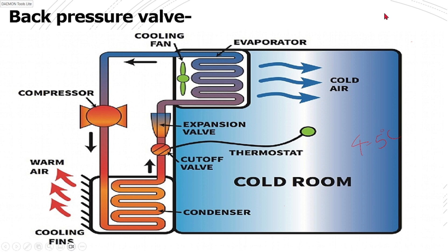Let's see what is a back pressure valve. A back pressure valve can be found in higher temperature rooms. If your cool room has to maintain a higher value — for vegetable handling or beverage rooms — where you have to maintain around 4, 5, or 10 degrees, then you can find the back pressure valve.